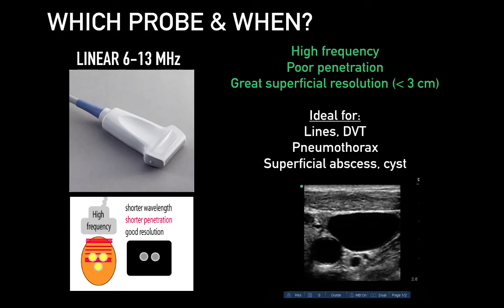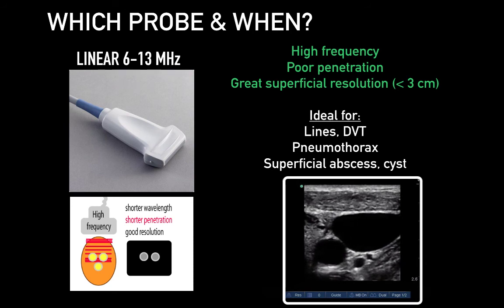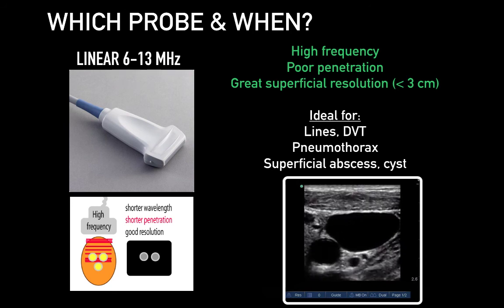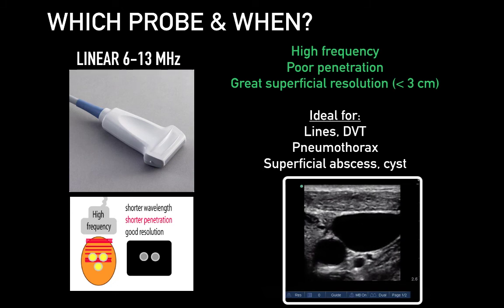So which probe and when? The linear probe is a higher-frequency probe, 6 to 13 MHz — often listed in reverse on the probe as 13, 6, so do not be confused by this. It is a high-frequency, short-wavelength probe and offers great resolution of superficial soft tissue including vessels, pleura, abscess, and cysts. As demonstrated on this 2D image, we can see that really high-quality resolution and visualization of soft tissue.